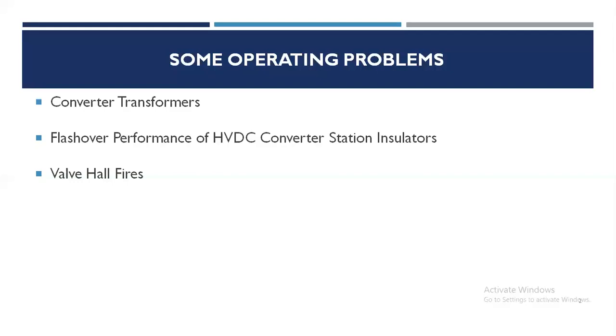Incidentally, Sylmar station was also affected by the 1994 earthquake. The building having mercury arc valves was extensively damaged, although the equipment damage was not as severe as in the 1971 earthquake. There were 3 fires in Nanqiao converter station in China that were caused by thyristor electronics, water-cooled resistors of the valve reactor, and water leakage. The fire in Sylmar station is also ascribed to thyristor electronics. The fire in Gezhouba converter station in China was caused by a loose connection between the reactor winding and copper connector.